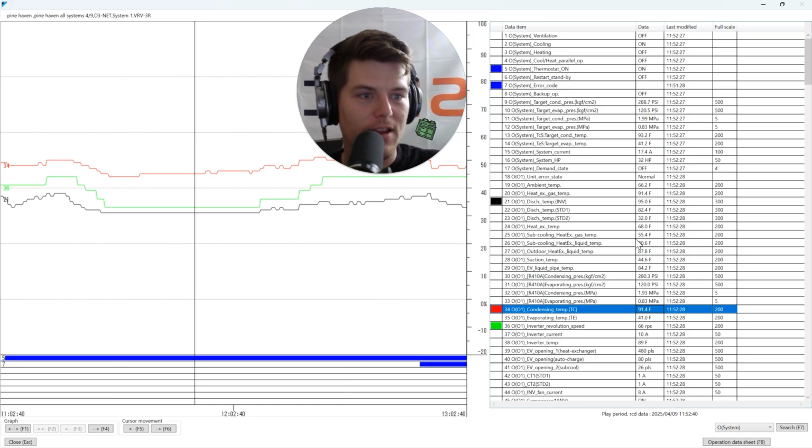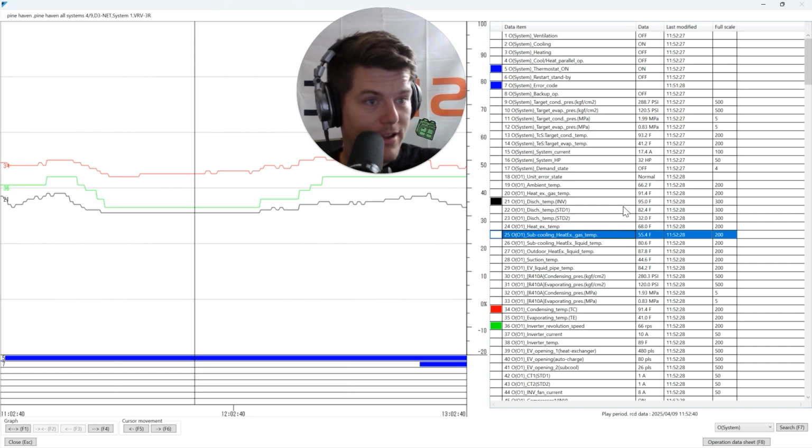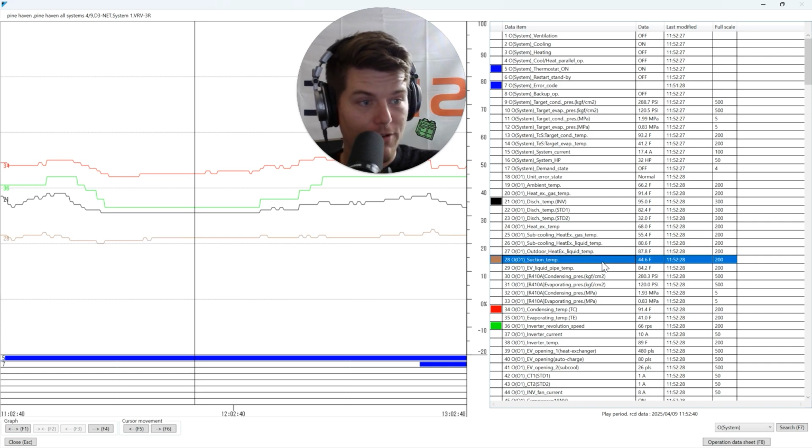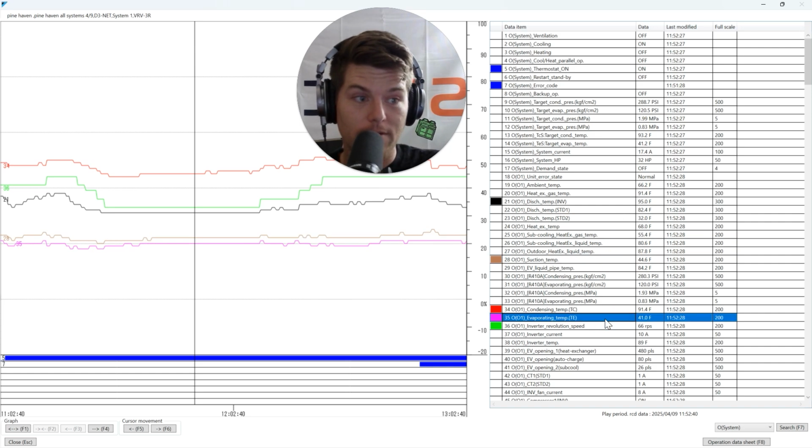One thing. It means we're compressing liquid. Well, how bad could it be? Let's take a look. Suction line temp here, 44, 41. Okay, well, now this is where a lot of guys like to throw shoes and bricks at me. 41 degree suction temp. 44 degree suction temp, 41 degree TE. You're going to say, well, it's above 41, so it's a vapor. But here's the thing. The closer this vapor gets to the evaporation temp, the more the mixture becomes a liquid. It's when it hits the evaporation temperature that we are 100% liquid.